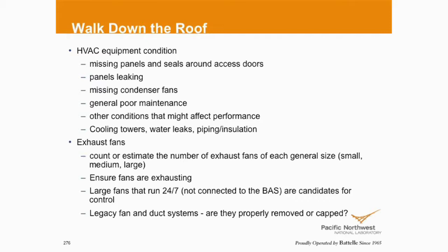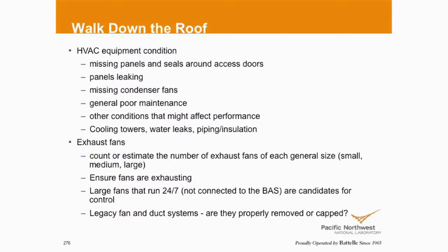If it's rooftop units, a lot of rooftop units, and air handling units for that matter, they all have doors and panels. Maintenance comes, they've got to do some repair. They pull the 6 or 8 screws off, zip, zip, zip, pull the panel off. They're done. Everybody pats themselves on the back. We greased everything. We changed filters, changed belts. We put the panels back on. Oh, it's time to go to lunch. We go zip, zip. We only put 4 screws in and off we go. So that happens. So do we see screws lying on the roof deck? Maybe those become puncture points for the roof. Now I've got leaks. More importantly, the panel may not be screwed on as tight. So I'm moving air through that unit, and now I've got some leakage that I created.